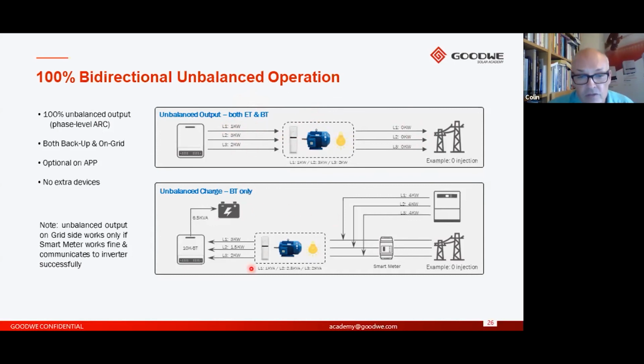Now, in the diagram below, just looking at the other side of things, when we're charging, we've got 4 kilowatts being generated. We don't want to export any power. We've got different load demands within this property, 1 kilowatt on phase 1, let's say 2.5 on phase 2, and 2.5 kilowatts on phase 3. So now, because we've got this unbalanced charge capability, we can take the individual excess energy from each phase, and we can use the combined output to charge the battery. So again, this is a useful feature to take all of that energy.